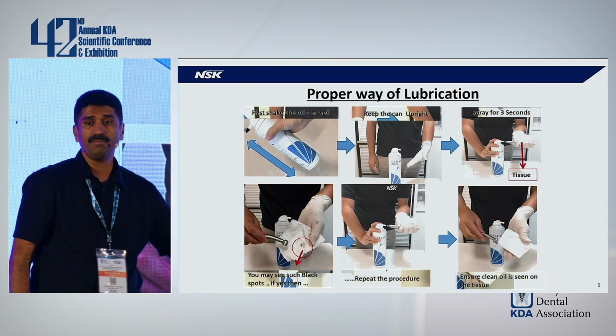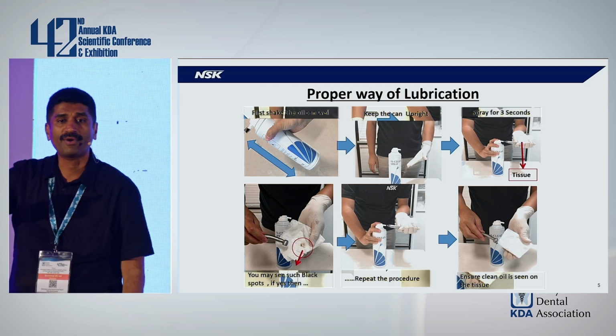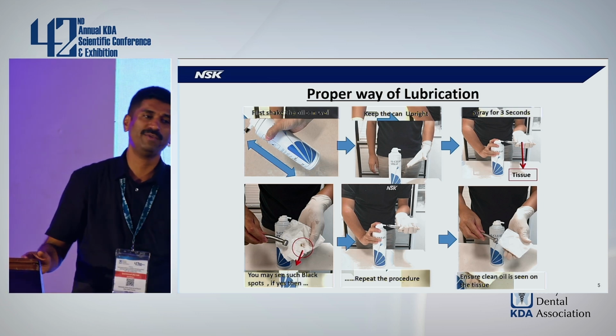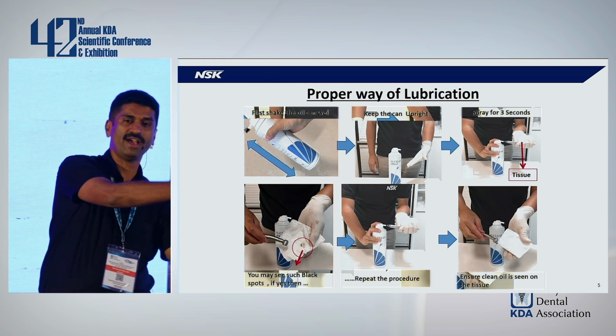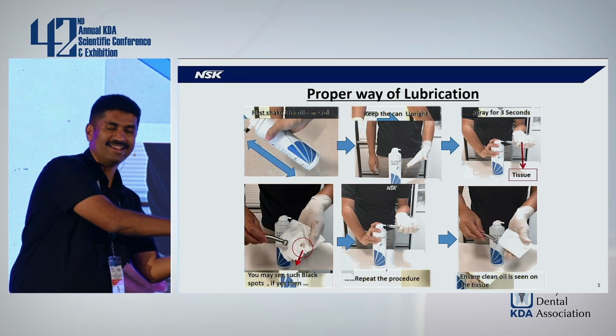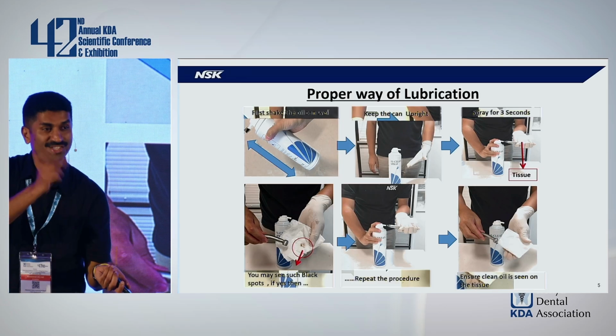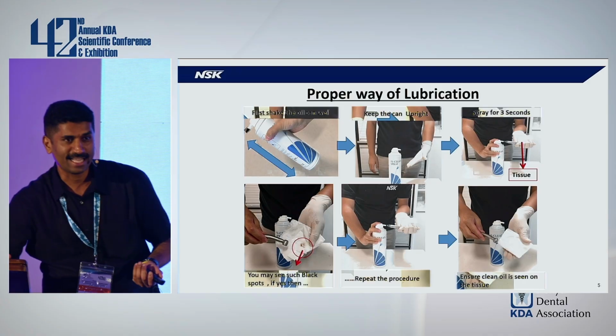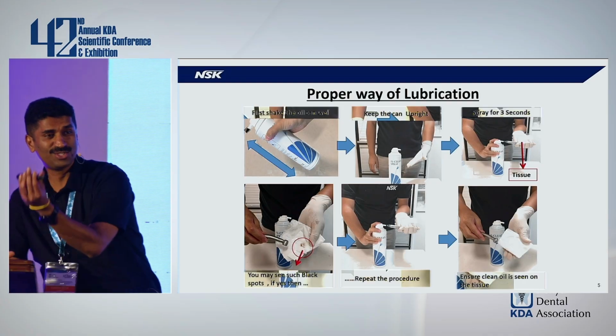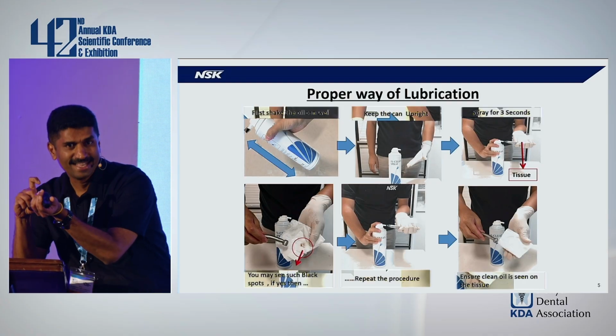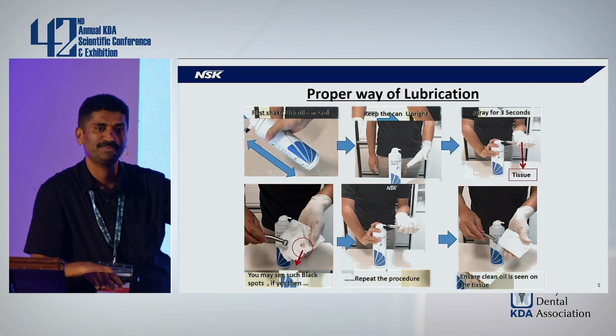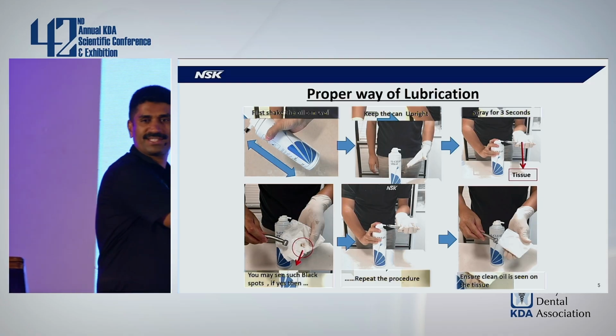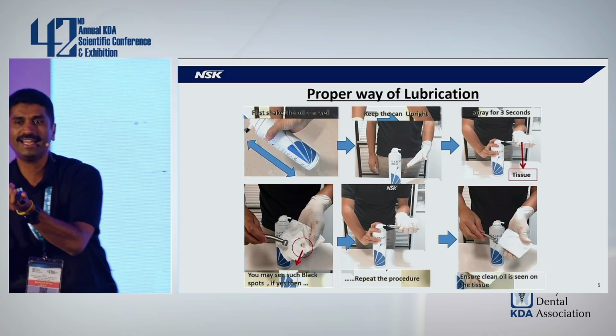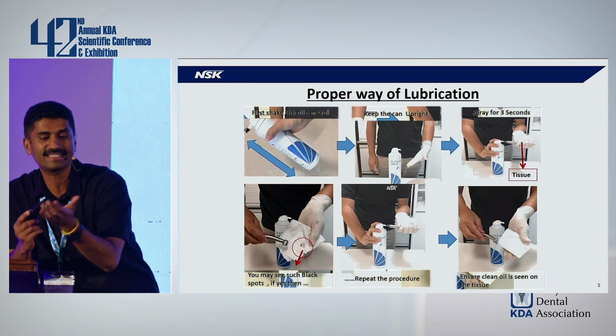Second step, very important, keep the oil can upright. What mistake we always make is we take the handpiece, we bring the oil can to the handpiece, and then we spray. Actually, this is the wrong practice. Shake the oil can, keep the oil can in upright position, bring the handpiece to the oil spray, and then spray for 3 seconds. Very important. It's not just like psst and leave it. No. You bring it and spray for 3 seconds.